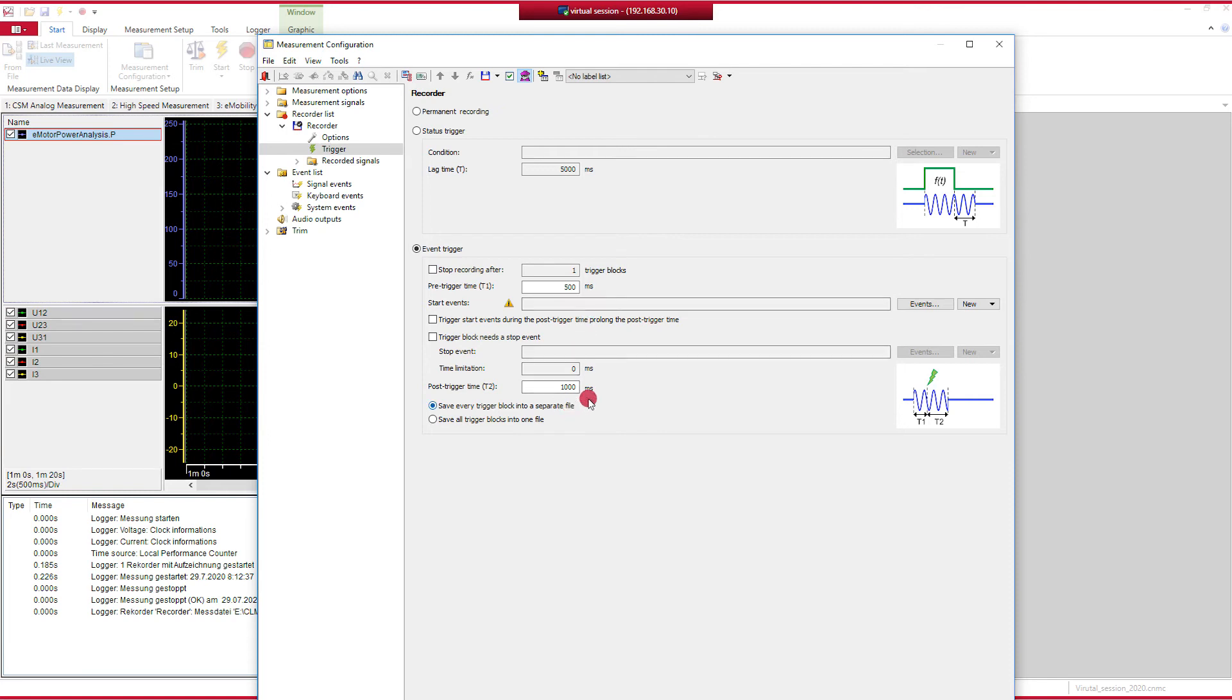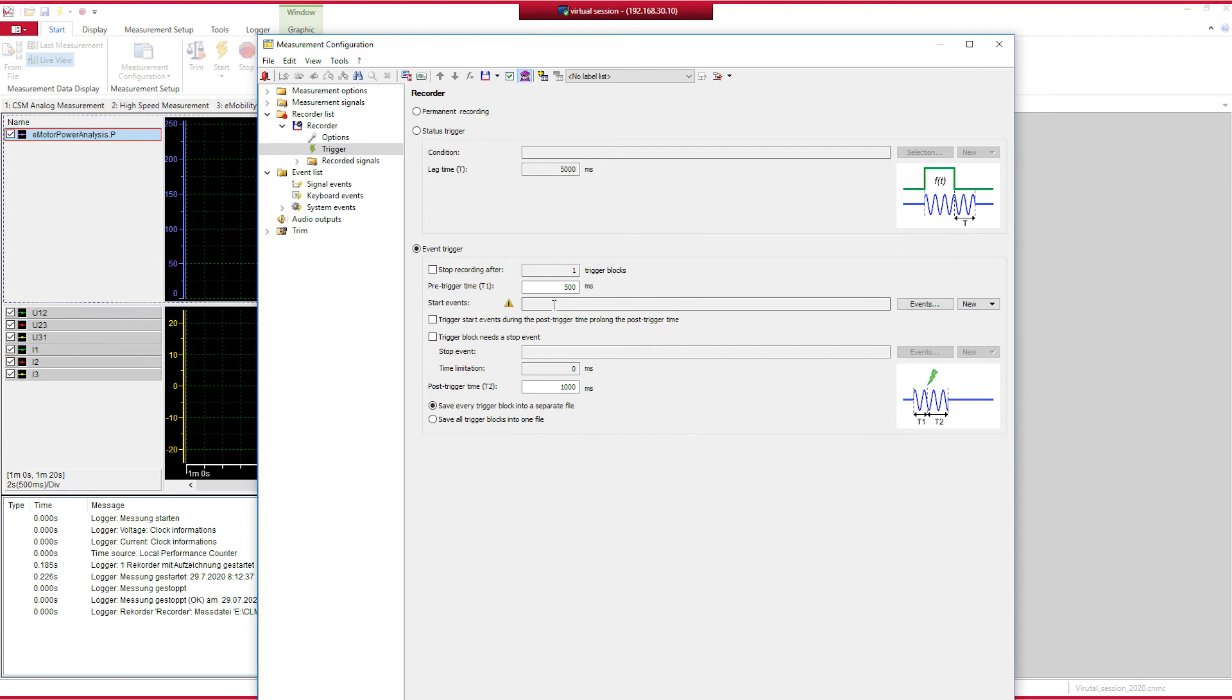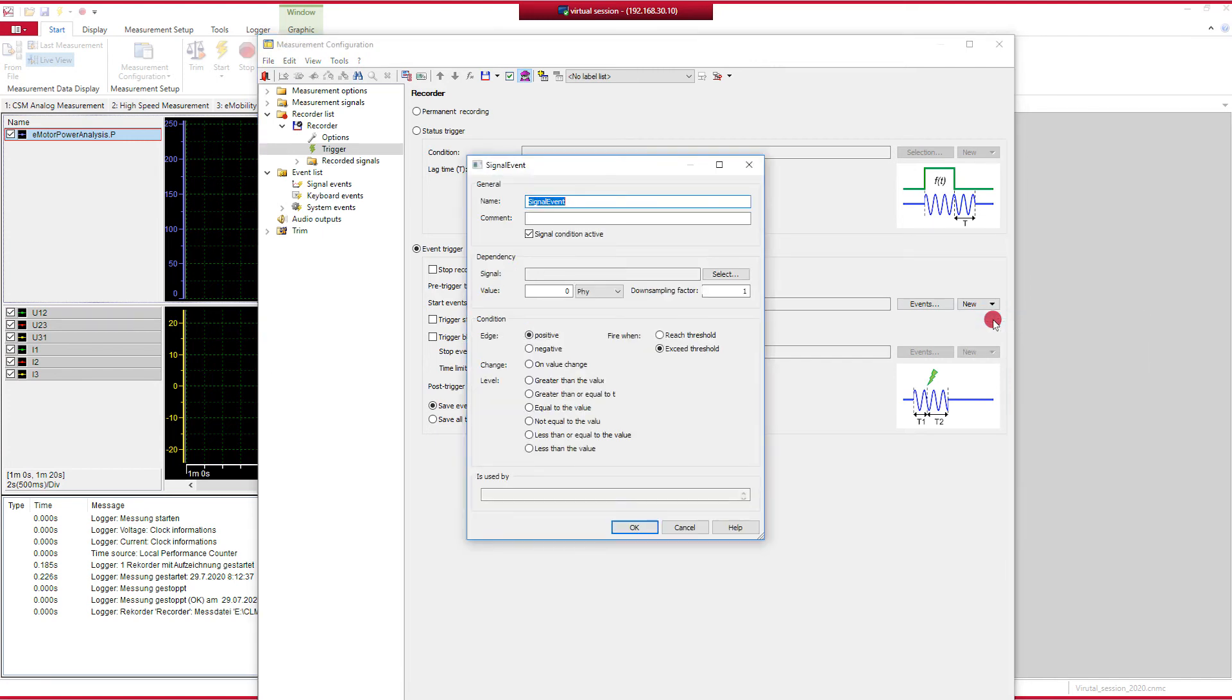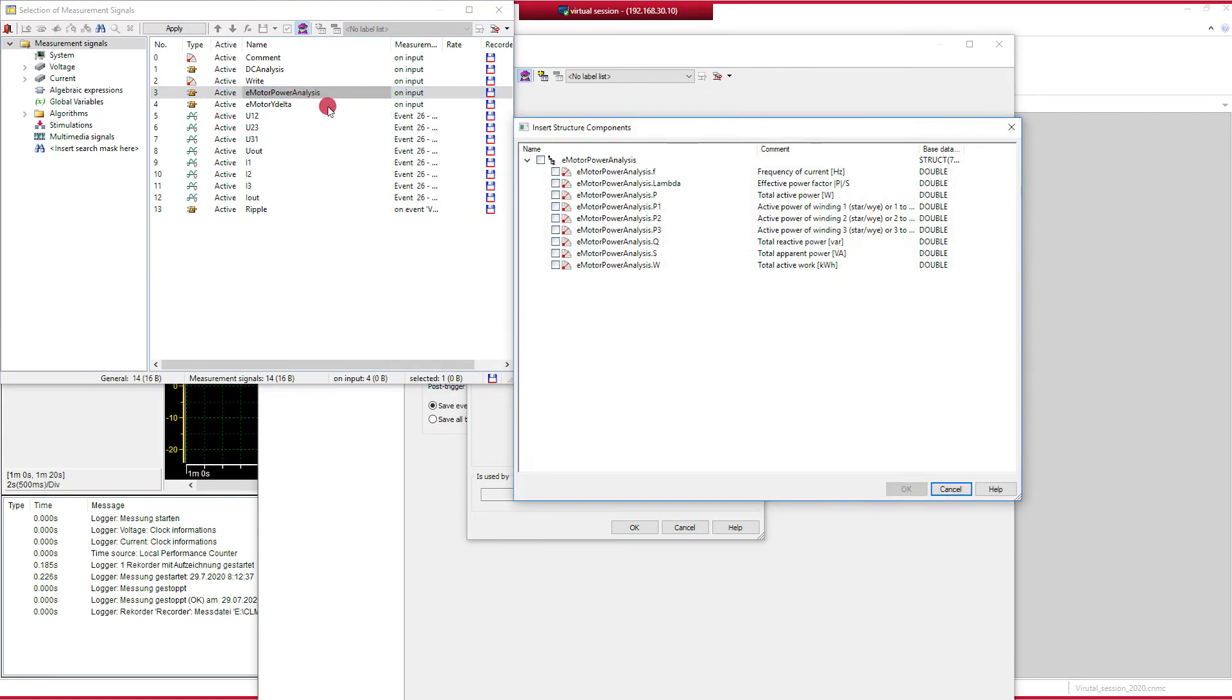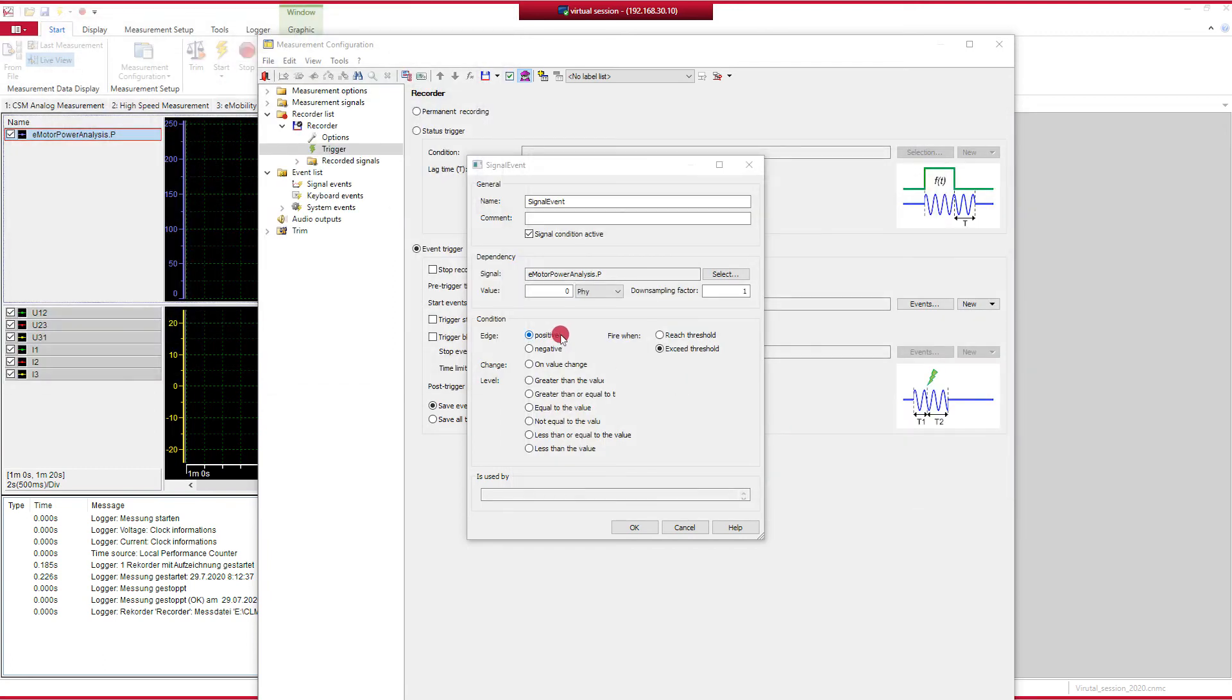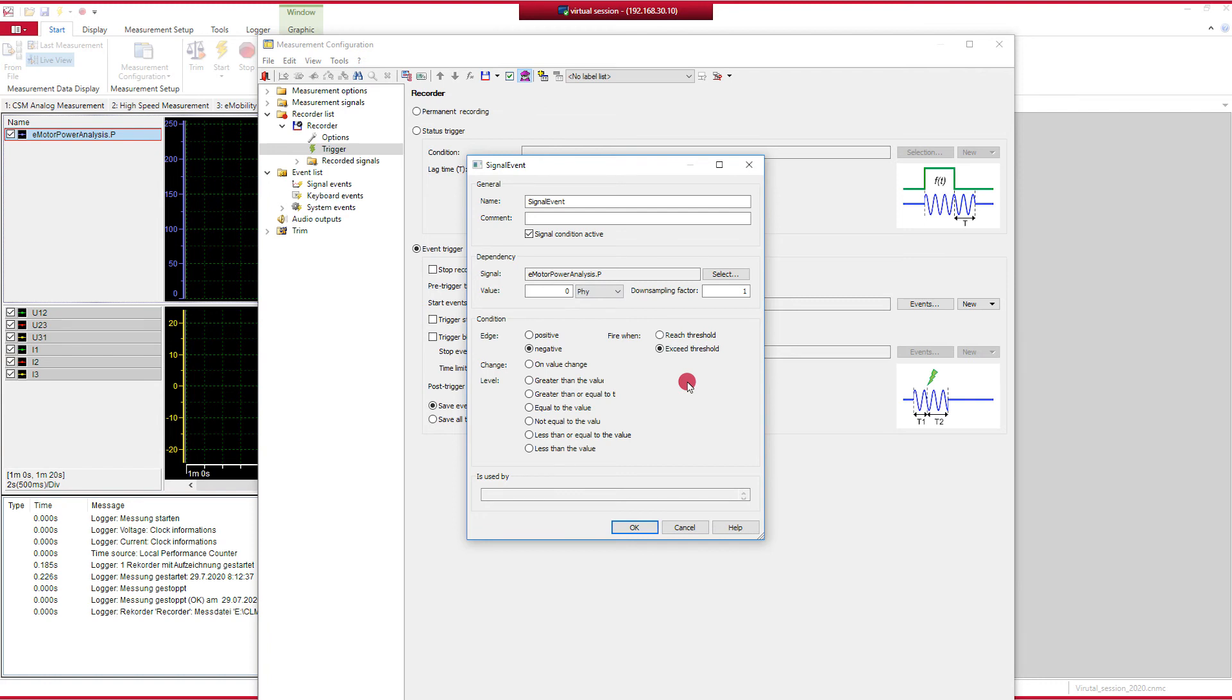In our case, we want to use the event trigger. And the settings are pretty fine for us. So half a second before the trigger event, the trigger condition is fulfilled, we already want to record the data. So this is kind of a ring buffer in the background. And we want to record for a second after the trigger condition was fulfilled. The main part now is to define the event that starts the trigger or that fulfills the trigger condition. We can do this by clicking on New, New Signal Event. And our signal that should get the trigger going is our calculated power. So when we select a signal, we want to select this power. This is part of the motor power analysis, and it's the P here. Say OK. And now we have to define what we want to see. And we want to see changes from positive values to negative values. So our threshold limit will be zero, zero watts. And when we turn on a negative slope, we surpass it on a negative slope, then we want the trigger to be fired.